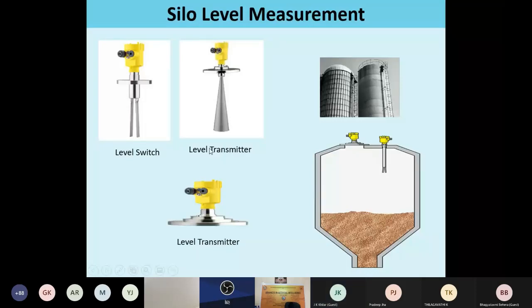The transmitter is analog type. What is the height of the level? It can be a 4 to 20 milliampere signal provided to the control room. But in the sensor, the level switch, it is a digital value, tuning fork type. If the silo level has not reached it, the sensor condition says it is vibrating. If the level reaches and touches this stem, the vibration will stop and the contactor position on the level switch will change and the PLC will give digital values. But here it will give 4 to 20 milliampere signals, so both analog signal and digital signal, depending upon the process, the PLC will get the input and process accordingly.